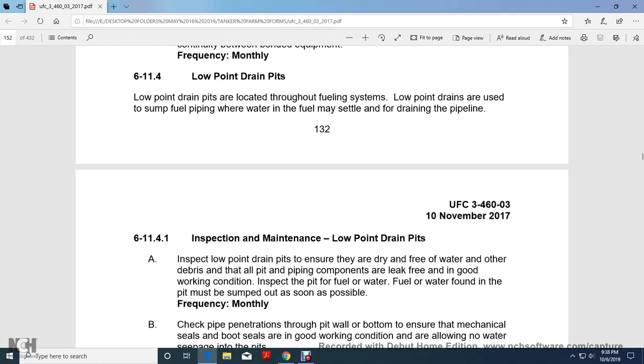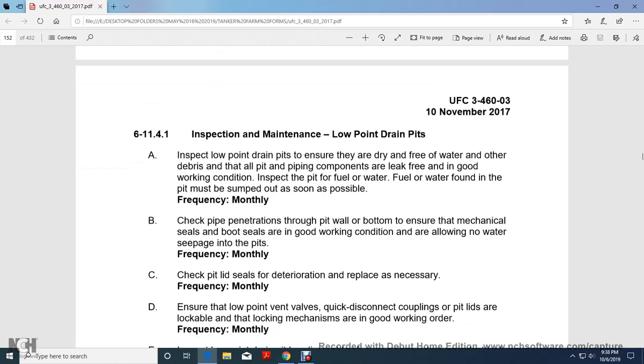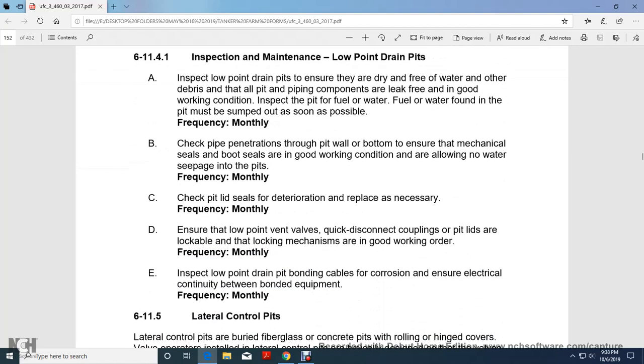Low drain pits. Low drain pits are located throughout the fueling system. Low point drains are used to drain water and fuel from the fuel piping at startup and for draining of the pipeline. Inspection and maintenance of low point drain pits. Inspect low point drain pits to ensure that they are dry and free of debris, and that all piping connections are free of leaks and in good working condition.